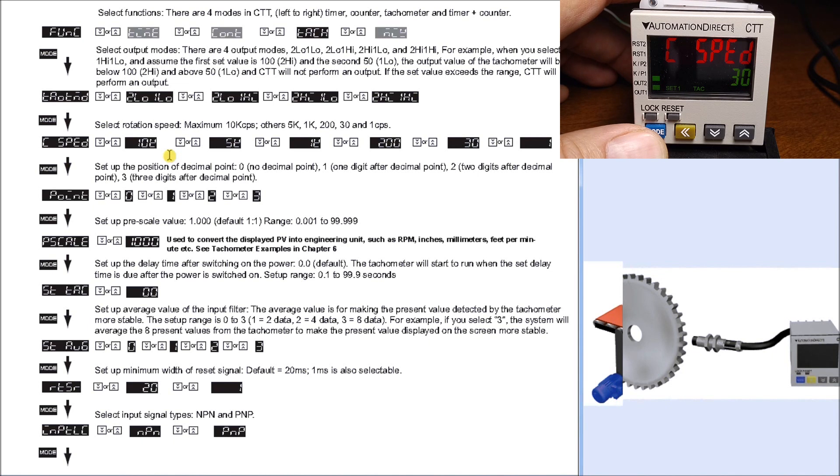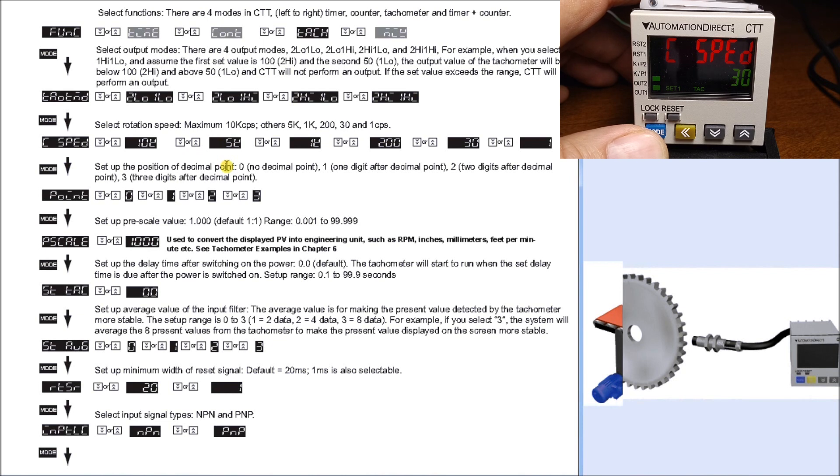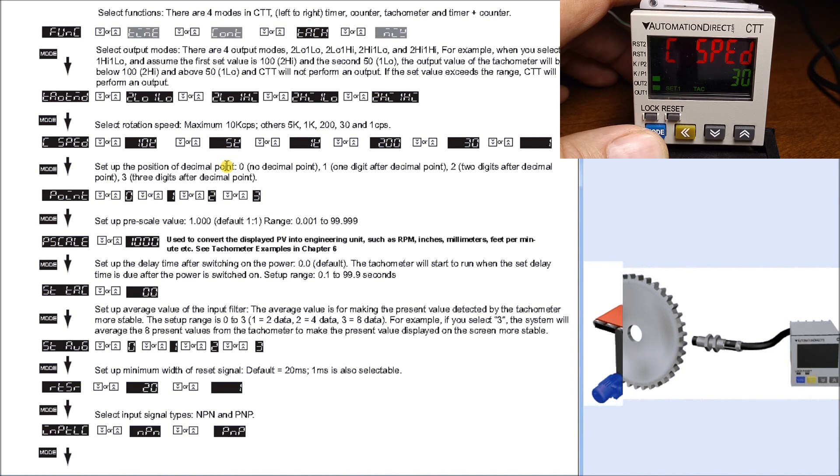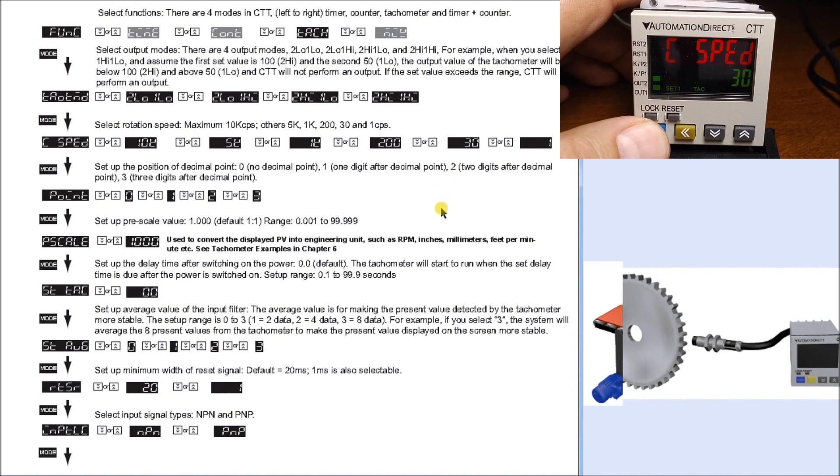In our particular case, we have a relay output from a PLC that will oscillate on and off, but the maximum number of times we could turn that relay on and off is somewhere around 10 times per second. Because of that, we will enter 30 as our value, which is what we have on the screen.